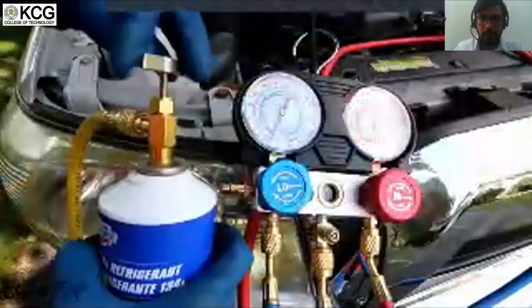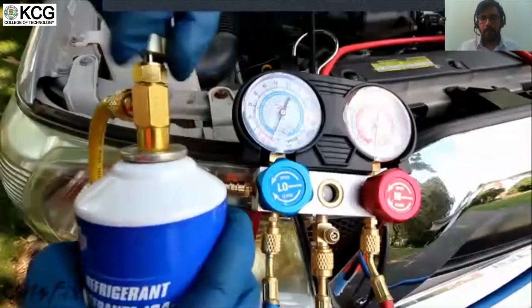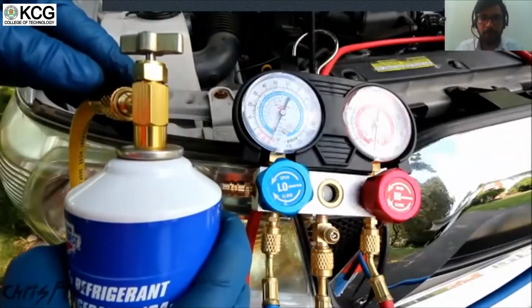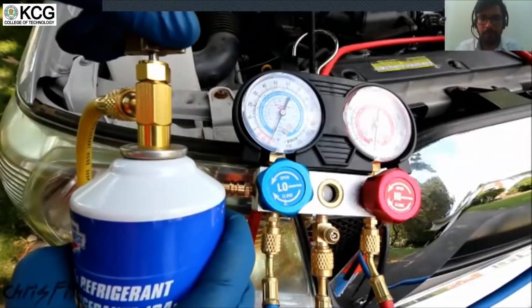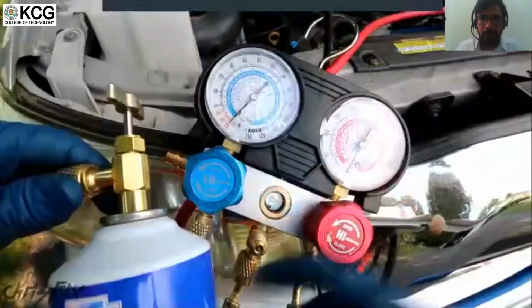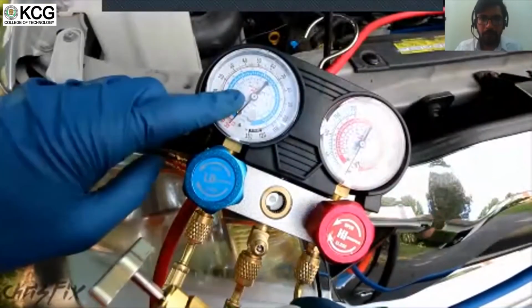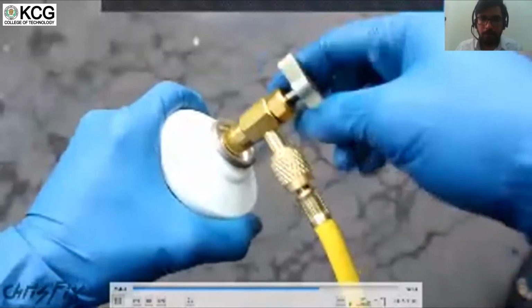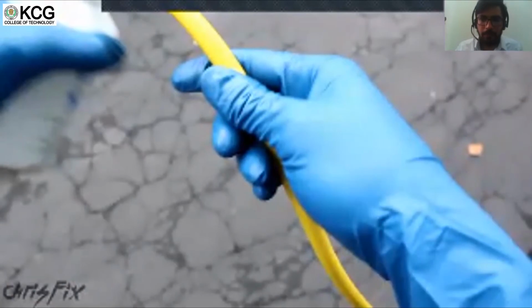Okay, good. So now we're going to screw down the adapter, which will pierce the can, and with this screwed down, this is in the closed position, so no refrigerant's going to come out. Also remember that the manifold gauges are in the closed position and holding vacuum. So now we're going to open up our can so we can purge the system. With this can in the open position, there's some refrigerant in this line, but there's also air in this line, so let's purge it out.